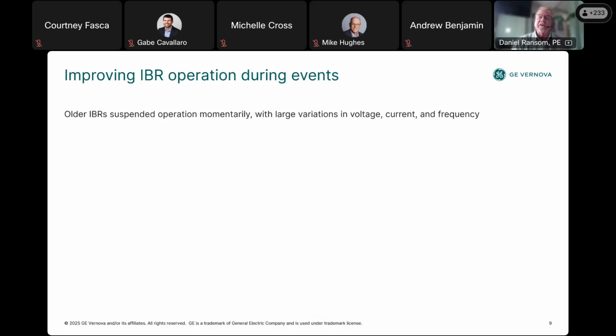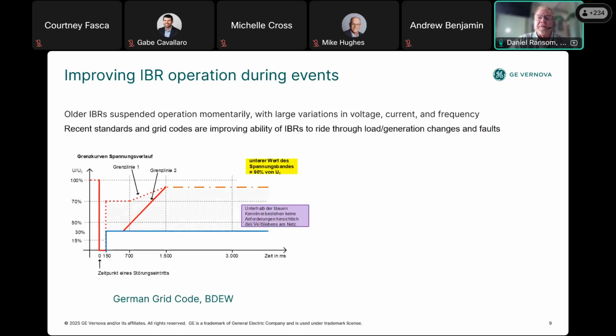So when a fault occurred, as I've mentioned, older IBRs suspended operation and had large variations in voltage, current, and frequency. And this caused incredible difficulty with conventional protection schemes because the relays didn't sense the faulted quantities for which they were looking. So recent standards and grid codes are improving the ability of IBRs to ride through load generation changes and faults. An example is the German grid code from the BDEW, Bundesverband der Energie- und Wasserwirtschaft, or the German Association of Energy and Water Industries.